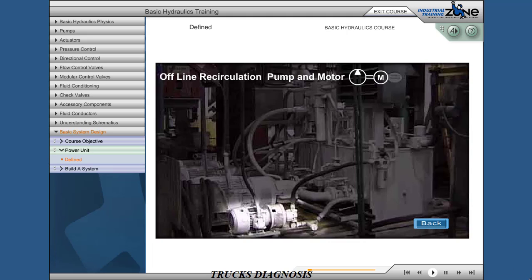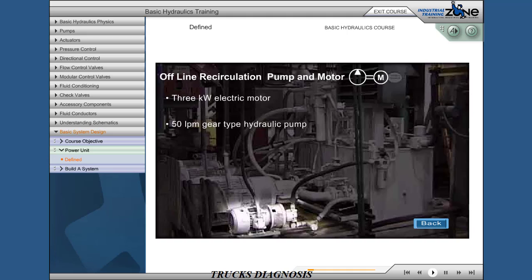Offline recirculation pump and motor. 3 kilowatt electric motor with a 50 liters per minute gear type hydraulic pump. Provides flow for the recirculation loop.